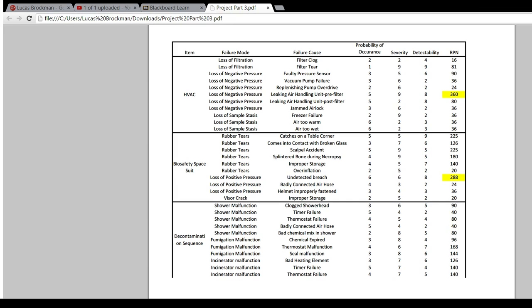Looking at the decontamination shower and shower malfunction, something that could actually hurt the system: there could be a clogged shower head, so not enough chemical comes out to neutralize everything. A timer malfunction, like what I just talked about, only has an RPN of 40 because it's not that serious. A thermostat failure could be bad too, if the chemicals weren't hot enough to kill what they needed to kill.